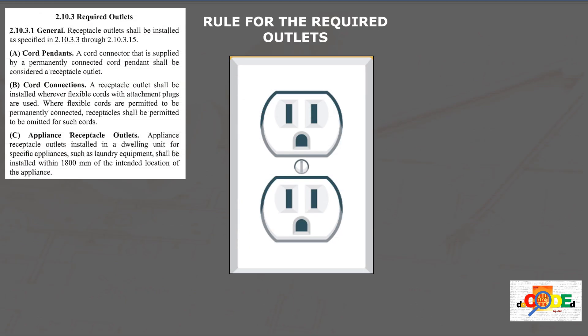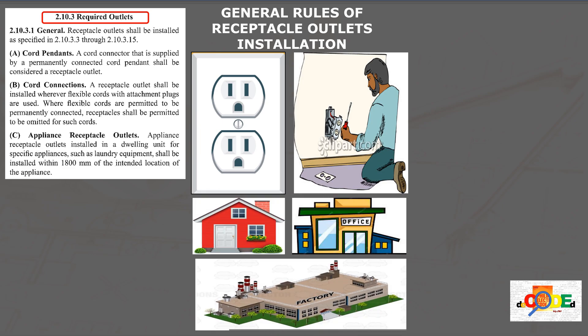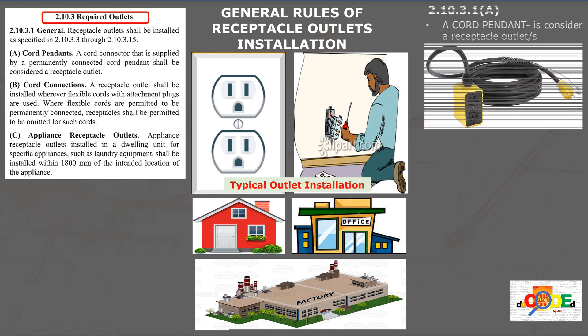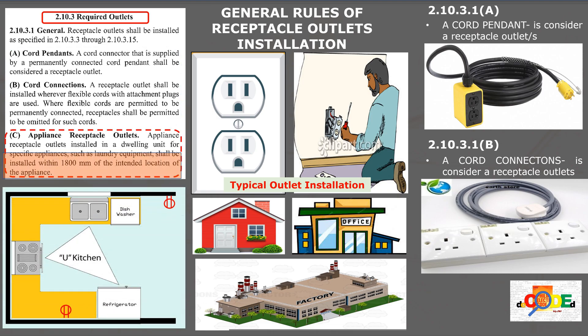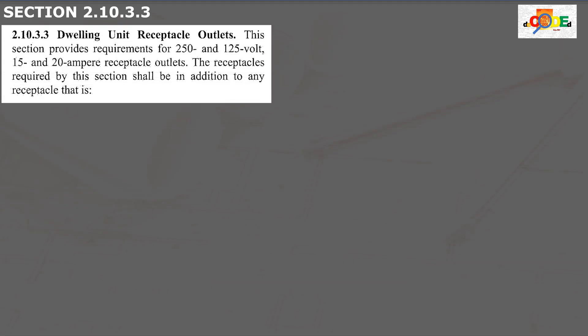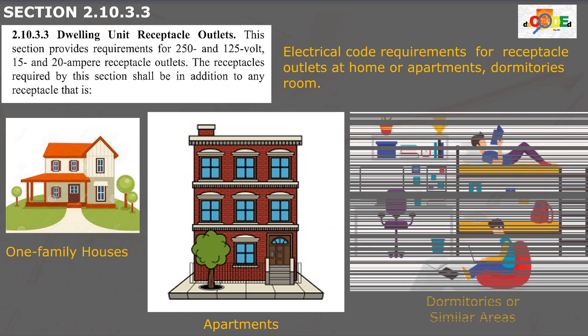What are the code rules for the provision of receptacle outlets? In section 2.10.3, Required Outlets, this section covers the general rule that applies to the installation of receptacle outlets in any type of occupancy or premises. The code also permits cord pendant and cord connection outlets as receptacle outlets. An outlet dedicated to specific appliances in dwelling units shall be installed within 1,800 mm from the intended location of the appliance. For dwelling unit requirements, we refer to subsection 2.10.3.3, which sets forth rules for one-family residential units, apartments, dormitories, and similar areas.